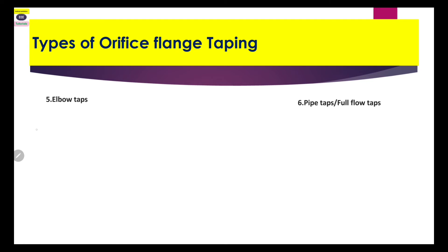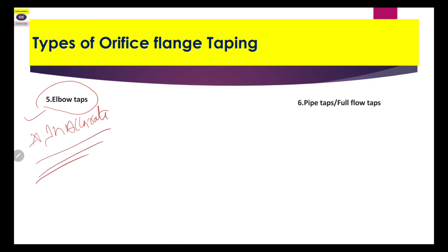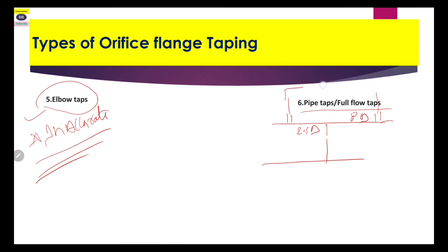The next type is elbow taps. Elbow tapping is generally not used in some places because it is highly inaccurate, so elbow type orifice flange is generally not recommended. For pipe taps or full flow taps, when your orifice is installed, the first upstream tapping is at 2.5D and the downstream tapping is at 8D. So these are the types of orifice flange tapping.